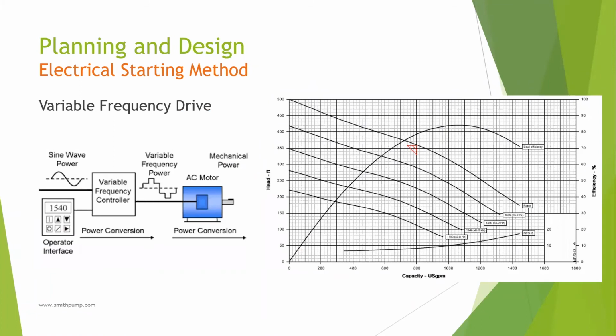And finally, the VFD. The variable frequency drive allows for variable flow. They can save money operating at reduced speeds, and they also act like a soft start. They work best on systems with high friction losses. However, using them on a system with high static head, like this one, doesn't allow much turn down.